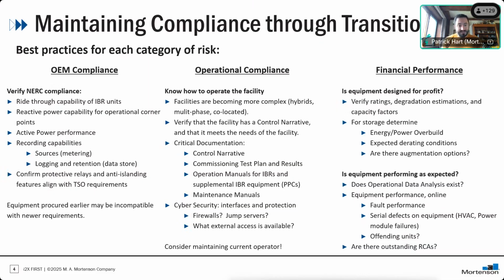And then finally, if there's any operational runtime, if it's in a commissioning phase where you can actually see how the system is running, I'd ask for operational data. First off, does that data exist? Look at equipment uptime, fault performance, any recurring issues like HVAC or power module failures, anything that would indicate a problem unit somewhere that needs to be addressed.